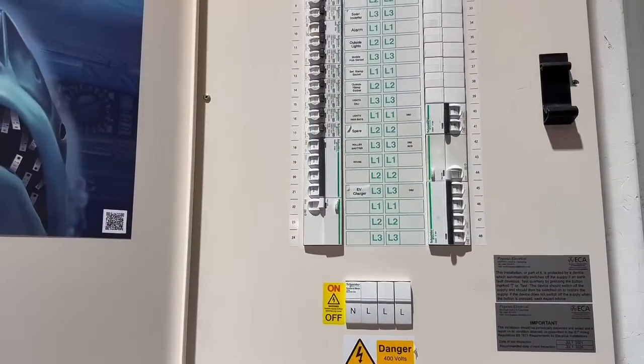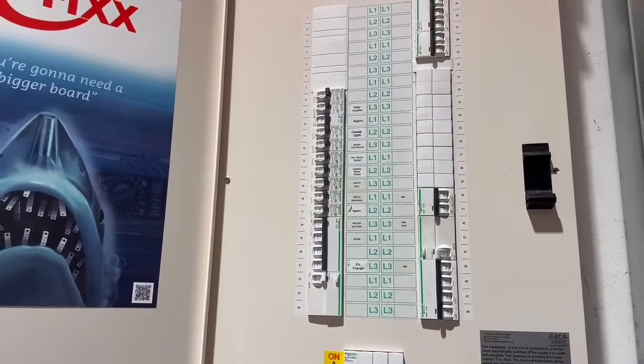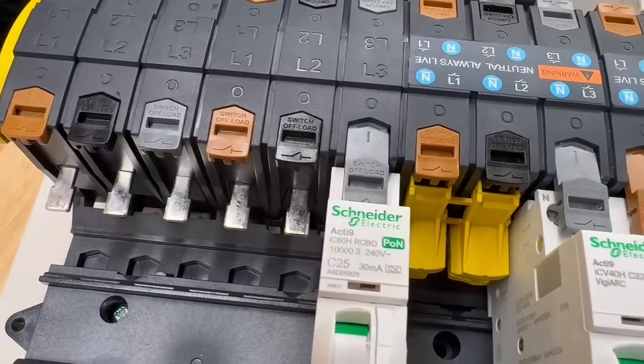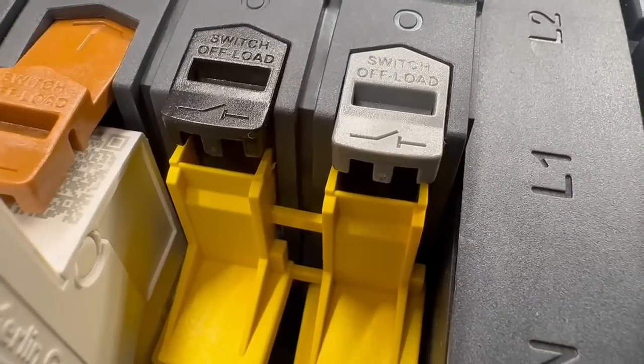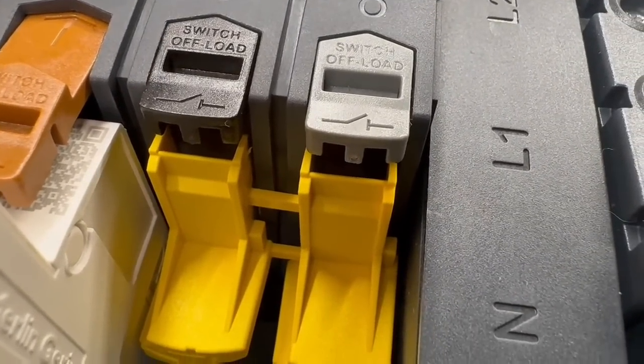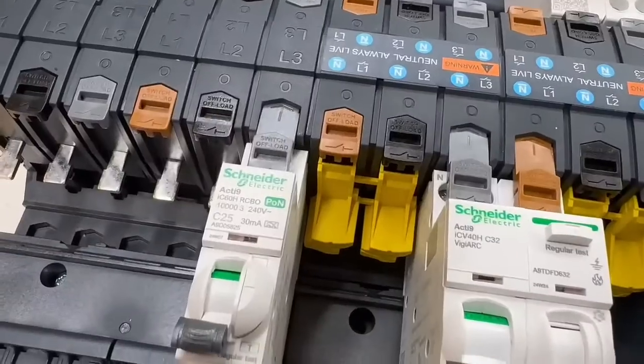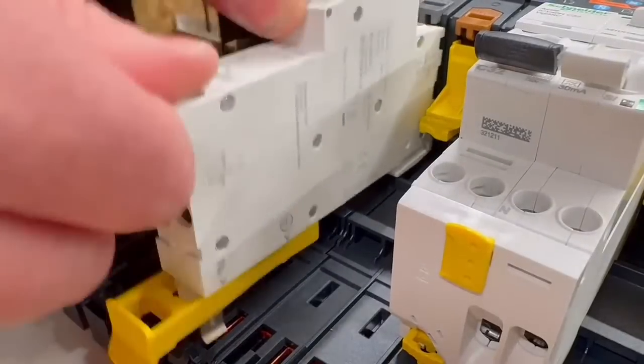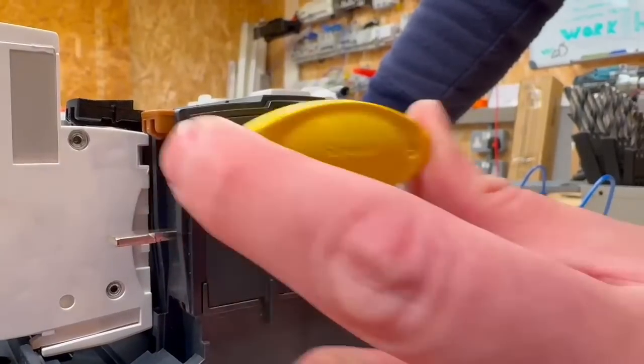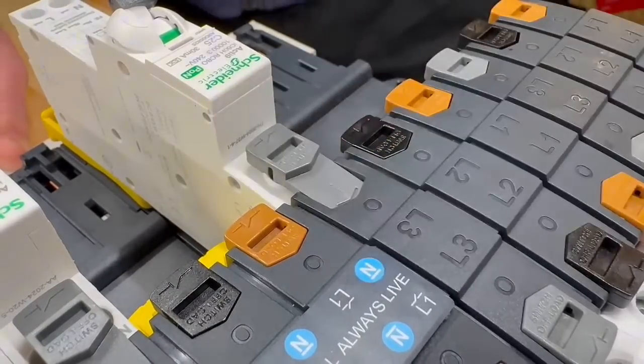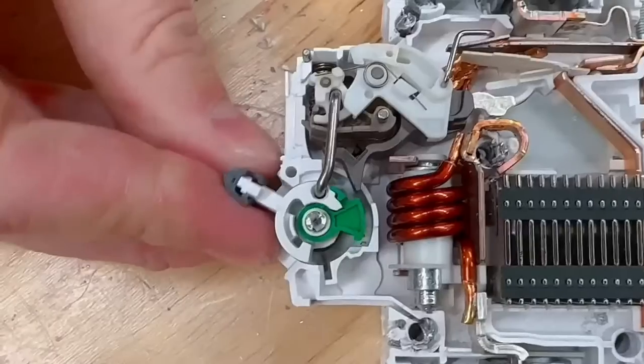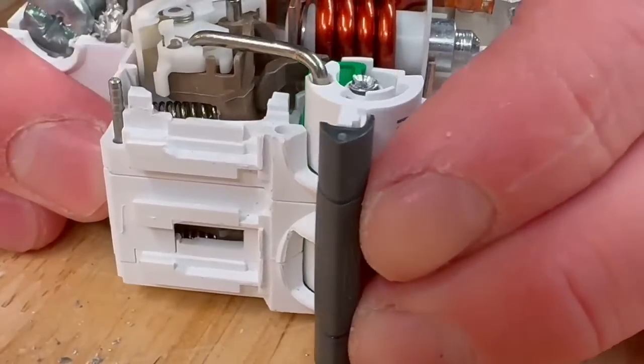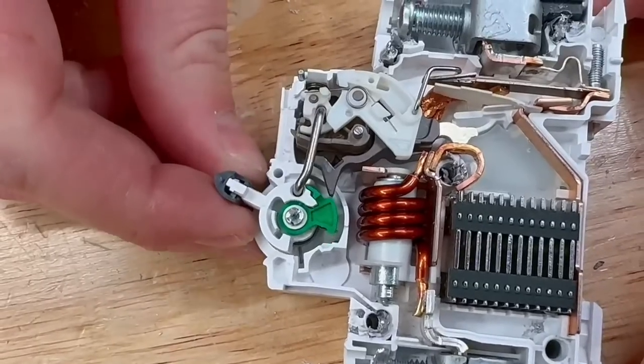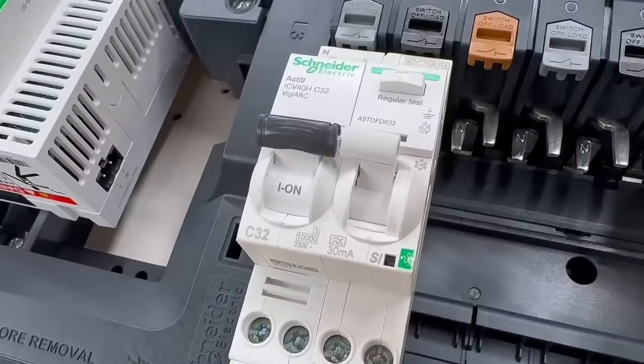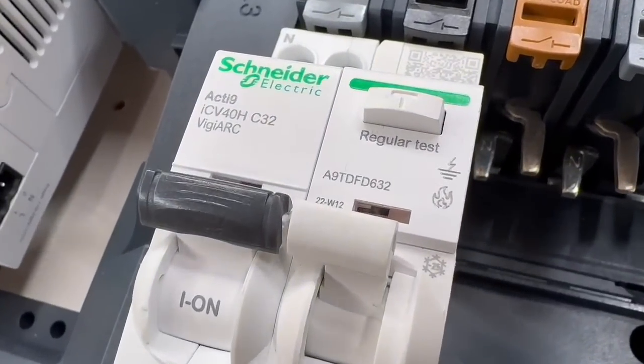Thanks to the innovative Iso bar, the Schneider Acti 9 range stands out with its top-notch electrical safety features. This system isolates the connection to the circuit protection device, increasing safety. Plus, it's certified to BS 60947-3 standards as an off-load isolator and can be locked securely in the off position. Every Acti 9 Iso bar P distribution board has a little lemon tool that makes opening and closing the Iso bar tabs a breeze. In Acti 9 devices, the green line is a mechanical shutter directly connected to the contacts. If you don't see it when in the off position, it's a sign that the contacts could be welded closed. The new Acti 9 active device can shoot you a message with real-time leakage current values and more.